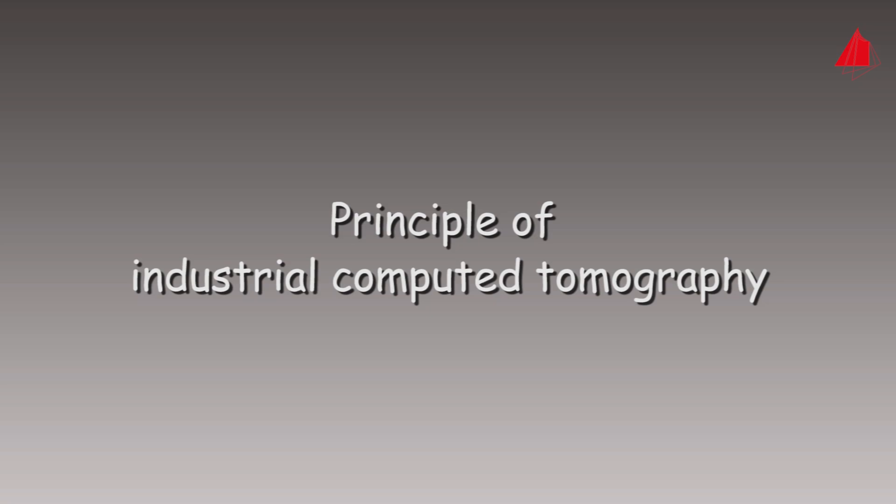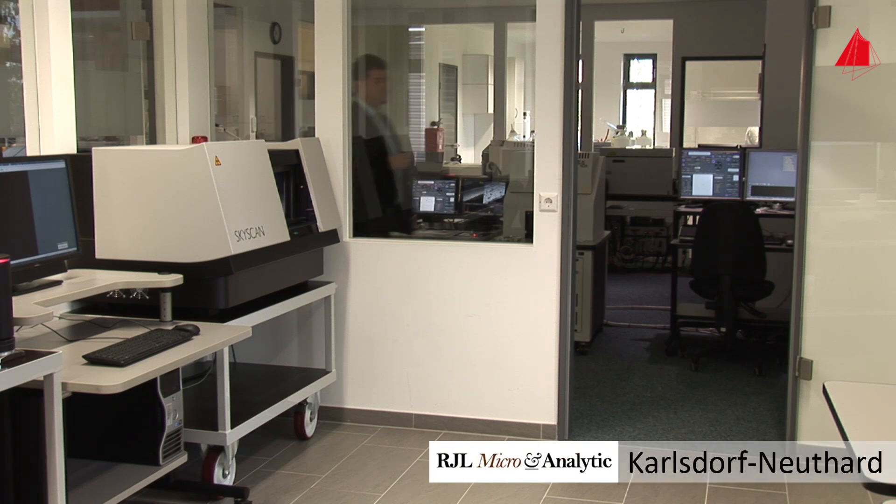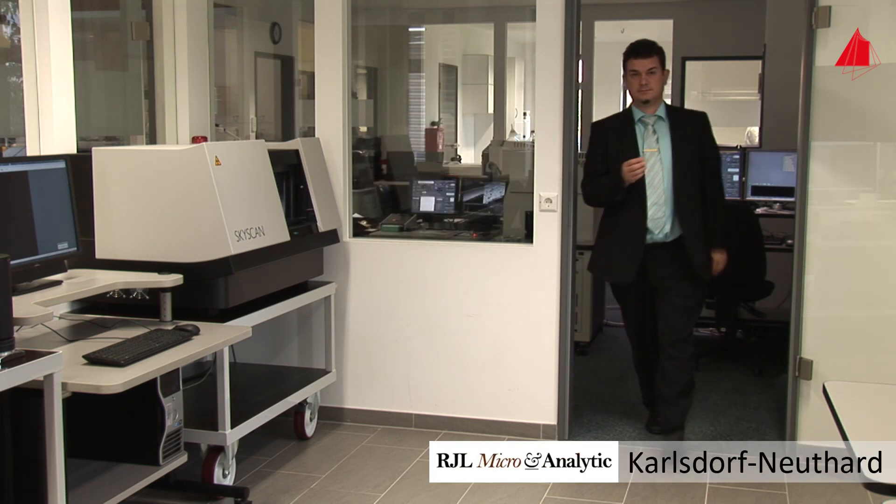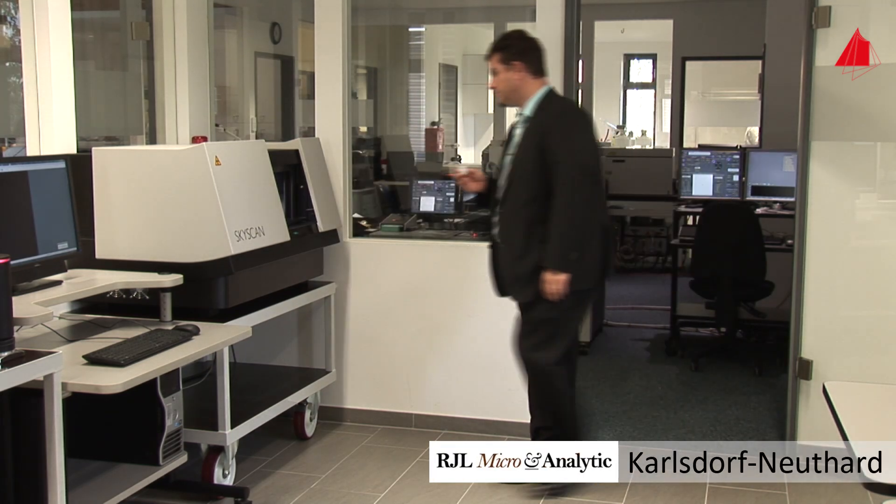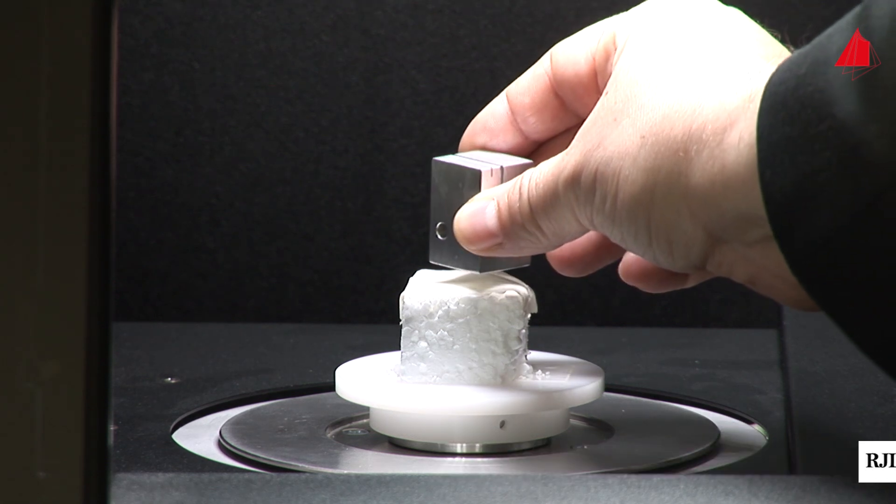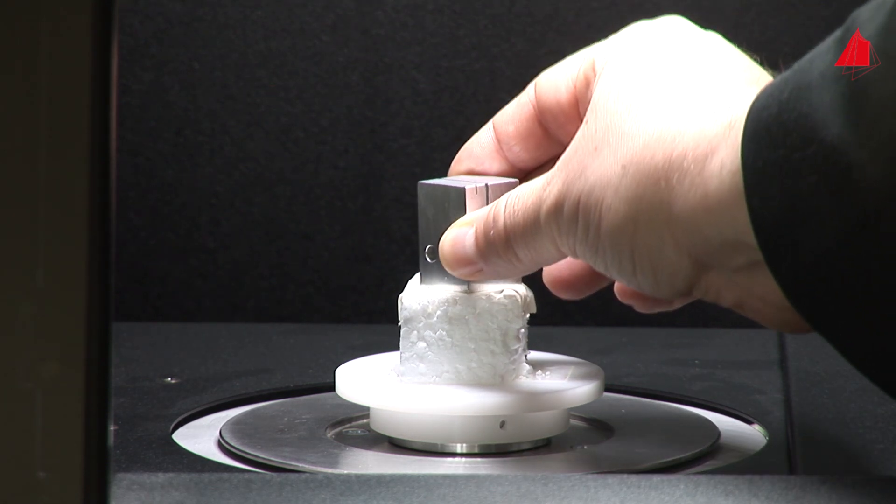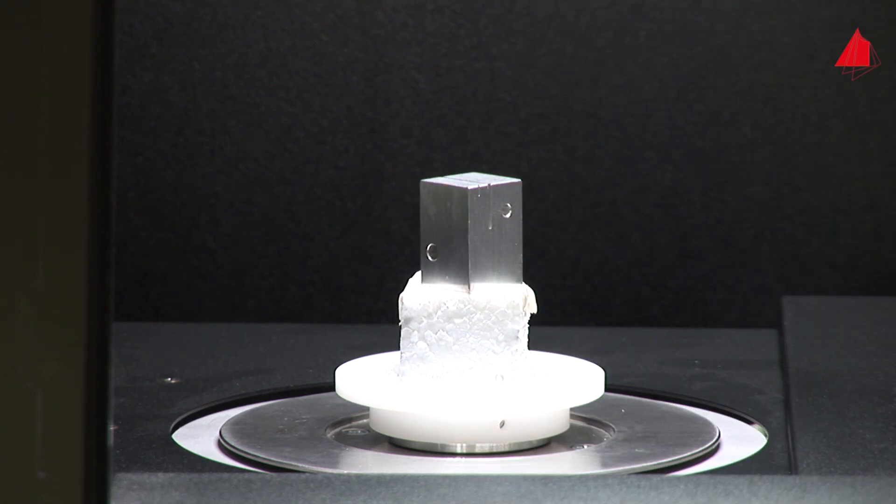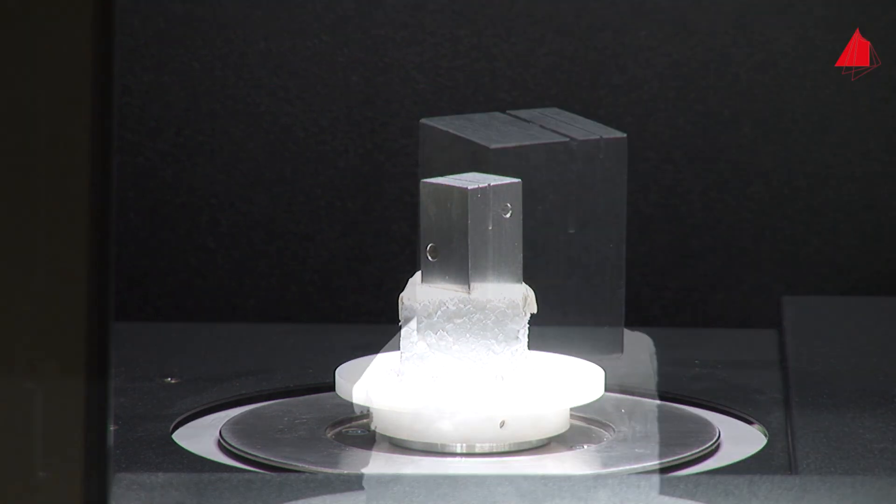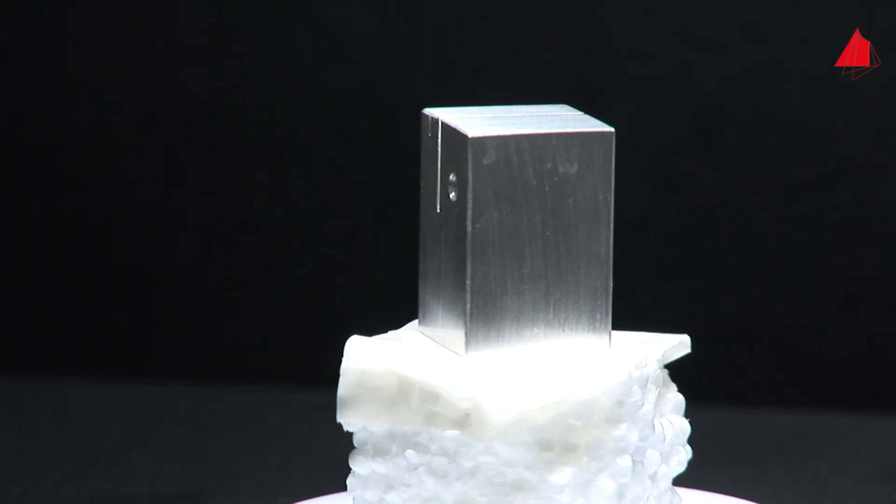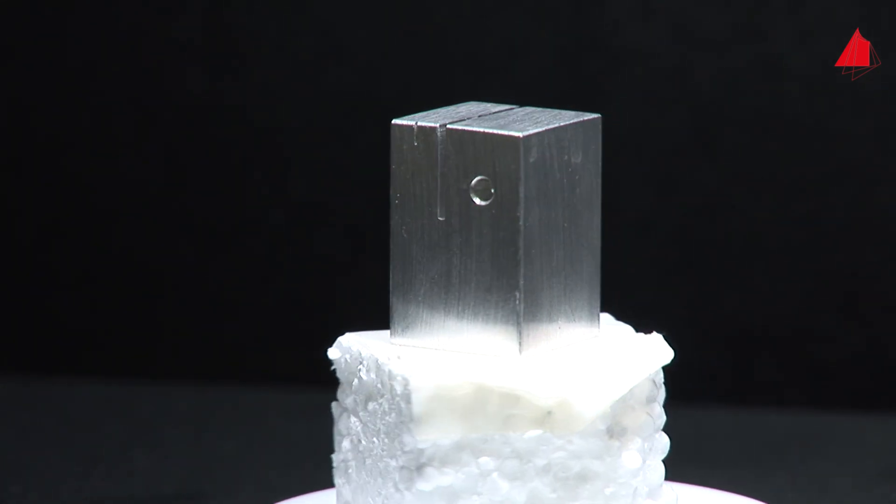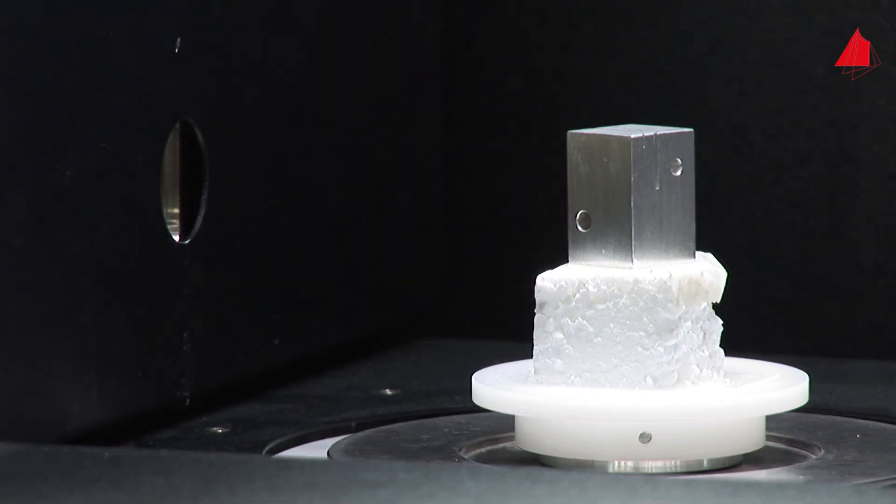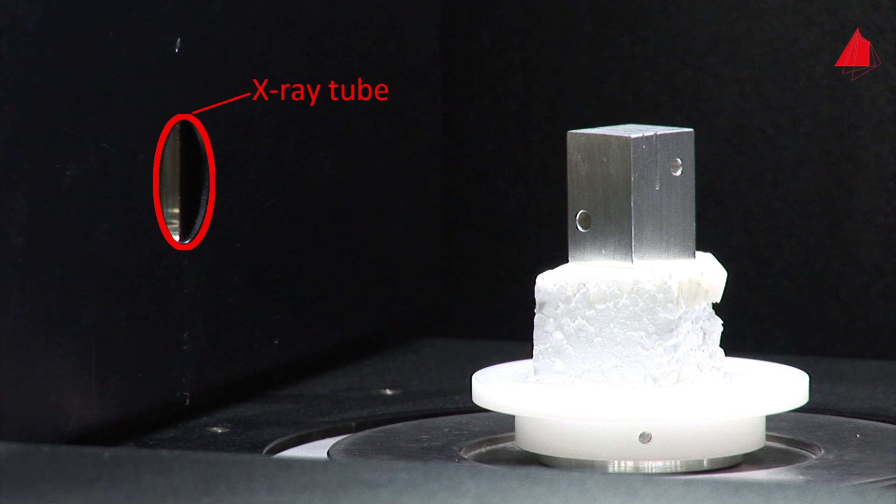How does it work? The aim of industrial computer tomography is to create a three-dimensional computer model of the sample. To explain the principle, we are going to examine a simple rectangular aluminum specimen. It is placed on a rotating sample stage. Various saw cuts and drill holes have been machined into the specimen.